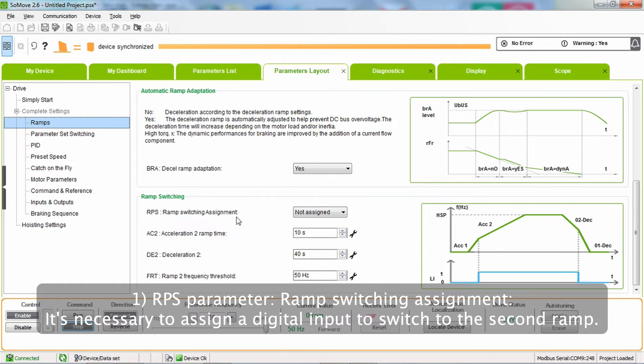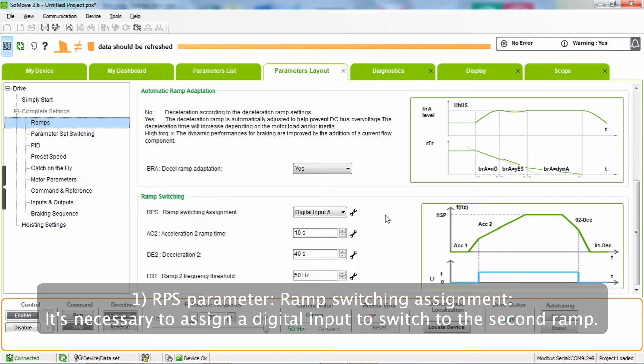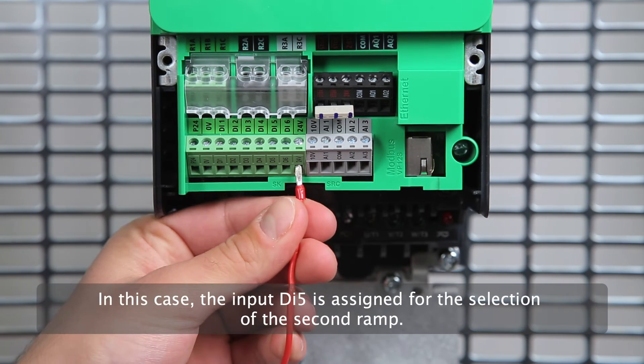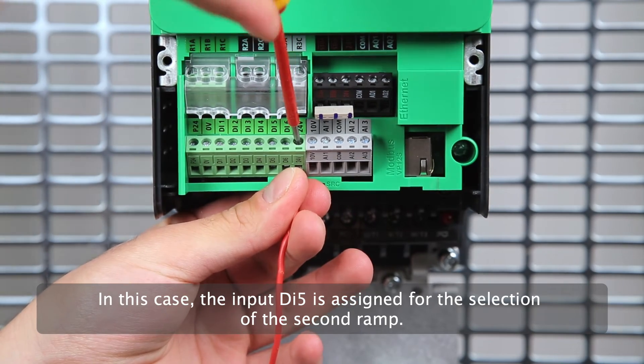Number 1: RPS parameter, ramp switching assignment. It's necessary to assign an input DI to switch to the second ramp. In this case, the input DI5 is assigned for the selection of the second ramp.